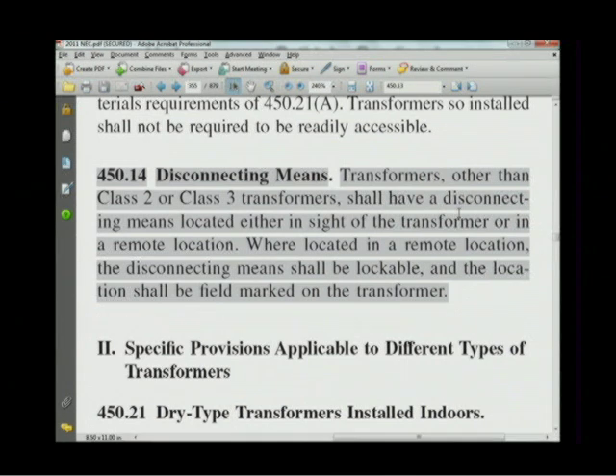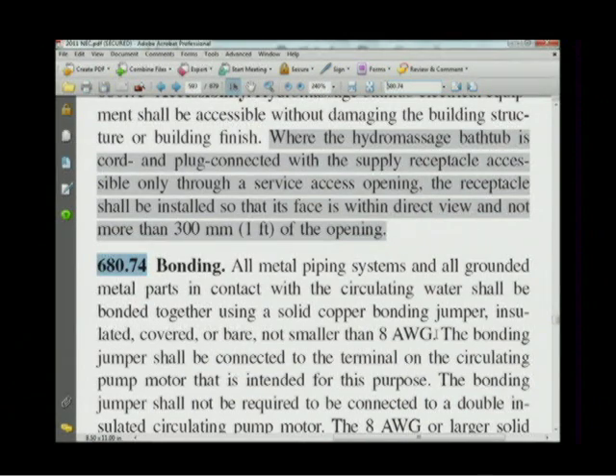Let's pull up the NEC 2011 electronic version and read 680.74 directly. It states: all metal piping systems and all grounded metal parts in contact with the circulating water shall be bonded together using a solid copper bonding jumper, insulated, covered, or bare, not smaller than 8 AWG. So we're talking about metal piping in contact with the water — and there are two things you have to bond if you have them: the metal piping system and all grounded metal parts in contact with the circulating water.